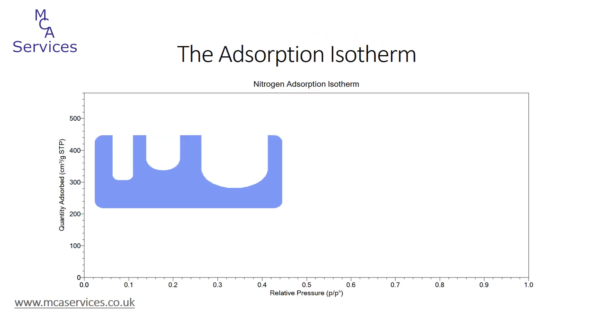At the start of the analysis, we will already have thoroughly degassed our sample, and this is to clean it through the removal of moisture or any other extraneous materials that are present — it's absolutely vital that we do this. The sample would have been placed into an analysis tube and then fitted to our analyser. At MCA Services, we've got two gas adsorption analysers, both manufactured by Micromeritics — a TriStar and a 3-flex instrument.